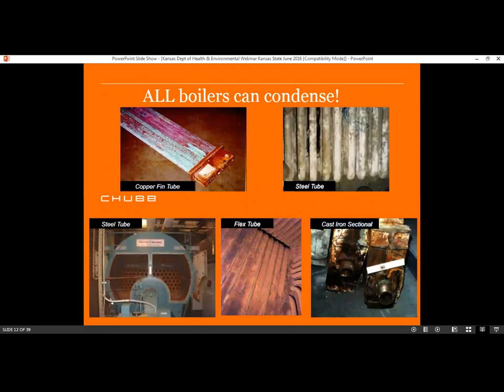All boilers condense. If you look at this slide, the copper fin boiler at the very top there, and you can see it's corroded. And these are basically a heat exchanger type tube that has fins on them. On the right-hand side at the top is the steel tube. These are division wall tubes, probably on a utility boiler, could be generating tubes. And then on the far left on the bottom is a Cleaver Brooks. This is what Keith has in his facility. This one here's a lot smaller though, but they're steel tubes. And you can see the corrosion on the tubes, and that's pretty much because it condenses, the water gets below a dew point and it sweats and causes condensation.